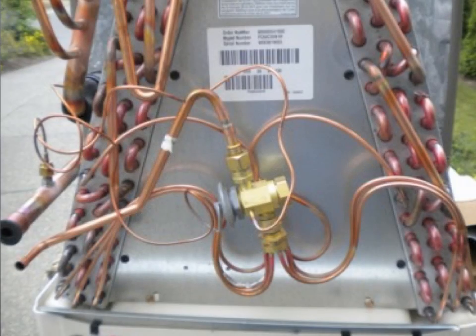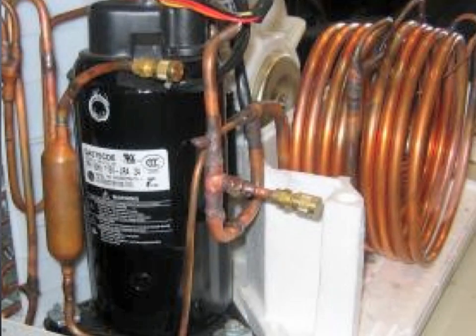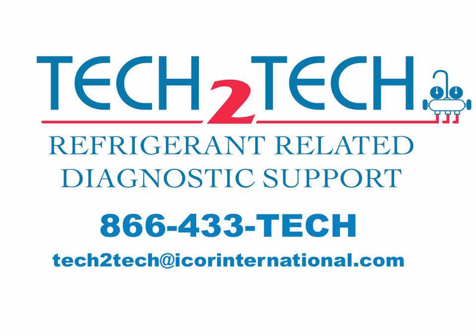Requirement 2: NU-22B is designed for use in systems utilizing direct expansion metering devices such as TXVs, fixed orifice, or cap tube. Requirement 3: It's not recommended to use this product in a flooded system. If you have a unique application you're considering for retrofit, please consult with an ICOR tech support member before proceeding.